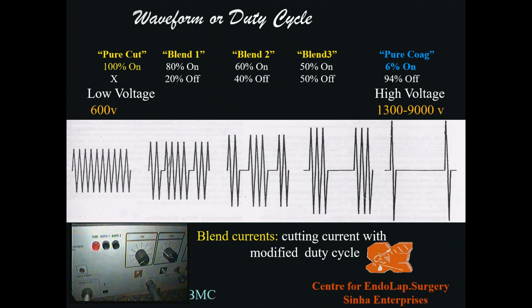What do we mean by duty cycle? Let's look at this figure. This is a low voltage current, continuous. This is an interrupted current, but the peaks are very high. So we are proceeding from a cut current to a pure coagulation current. So what is happening in a cut current? A continuous low voltage. In a coagulation current, an intermittent high voltage. Now, what does intermittent mean? Maximum time it is off. It is only 6% time it is on, 94% is off.